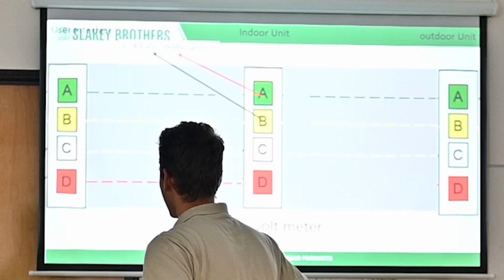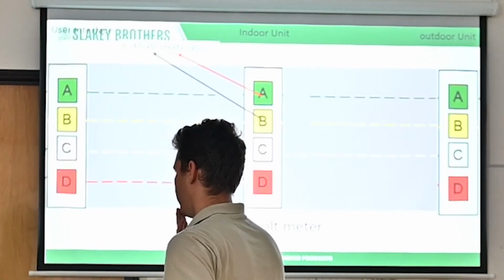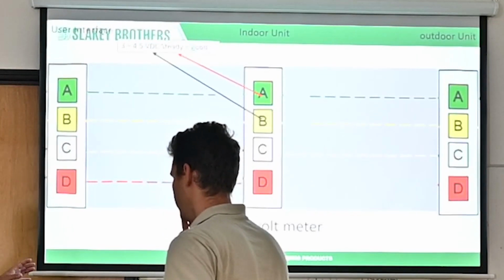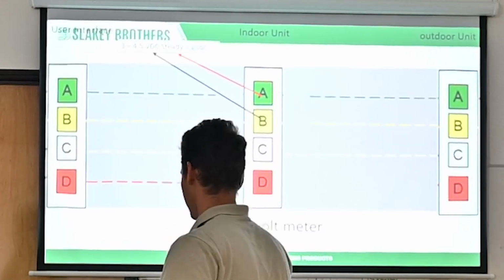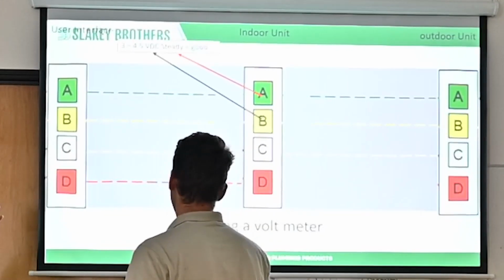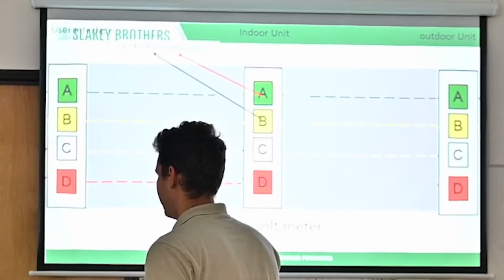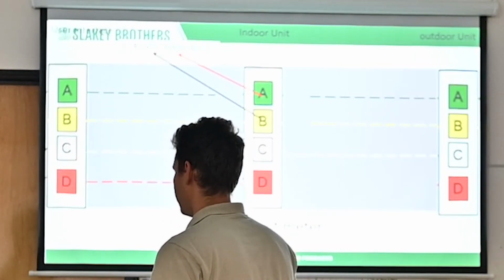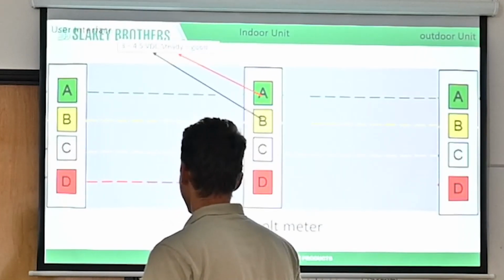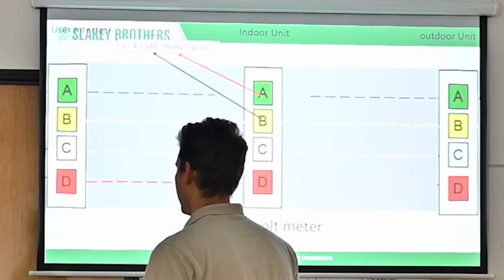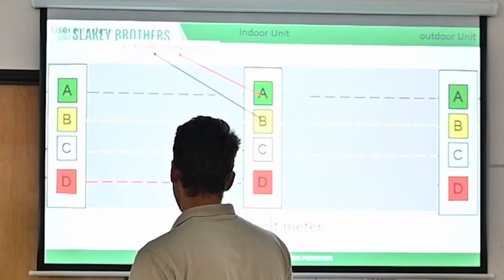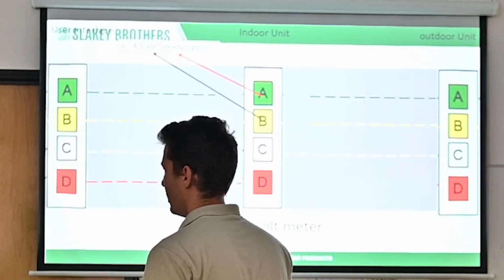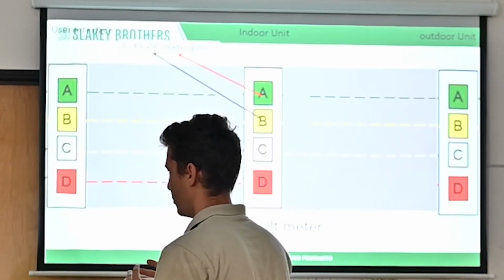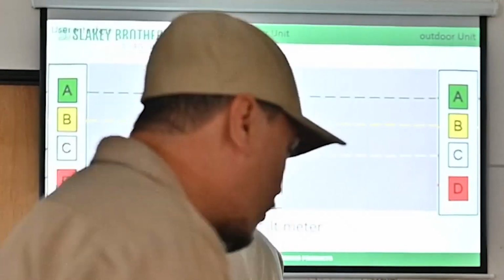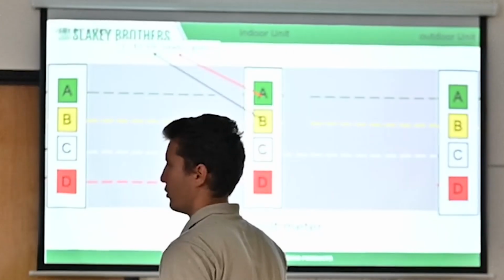So if you ever want to make sure that's what it is, you can put in a temporary thermostat. Just take the controller off the wall and hang it, something like that. And if it works great, then you know, all right, Mr. and Mrs. Customer, we've got to run a whole new wire now. There's something wrong with the wire. Yeah, gotcha. In this case, I think it's something with interference from the high voltage wire. I'm not sure because it's every 3 minutes.